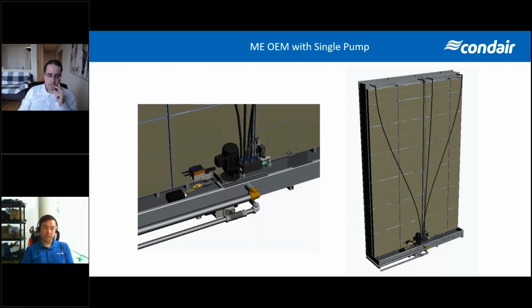So with this, what we've designed is effectively an OEM unit with a more traditional single submerged pump. And we have the ability to tailor this if they need stage control, if they just want on-off control as well. So the really great thing about these types of systems compared to your off-the-shelf, standard steam humidification systems is these are very, very scalable and very, very customizable as well. So that's just one of the options that we have available if you've got a client that doesn't want the full package with integrated controls. So that is something that we do have available there.